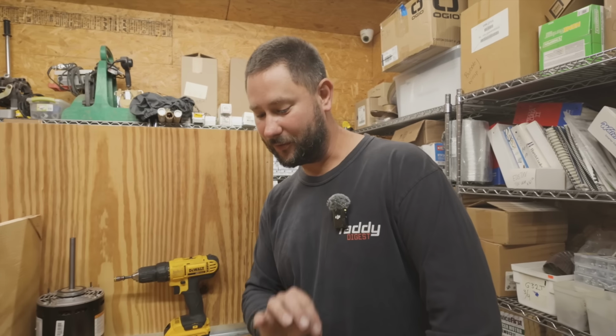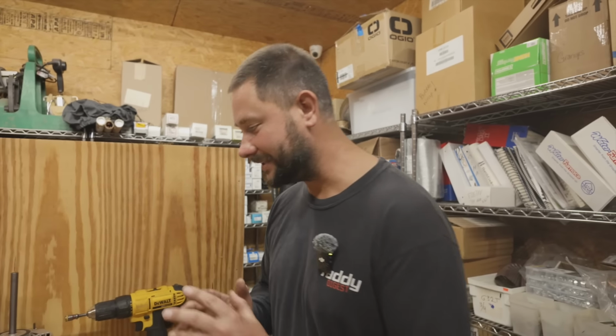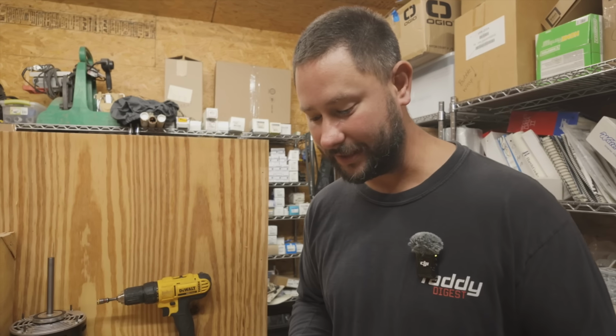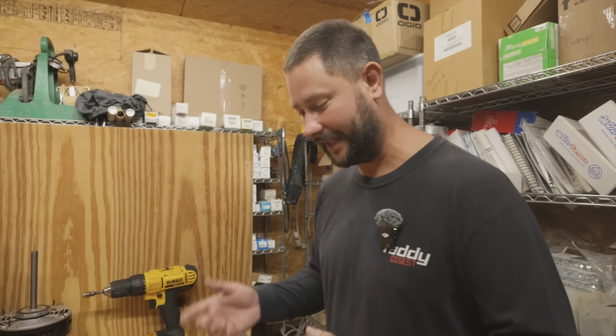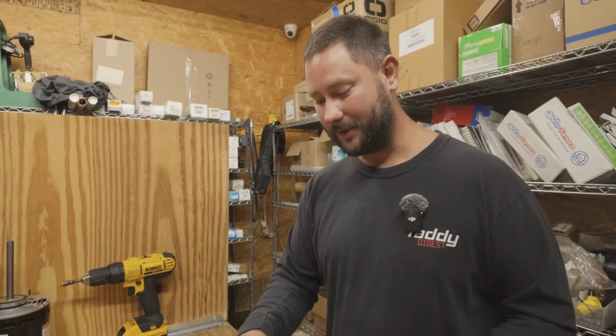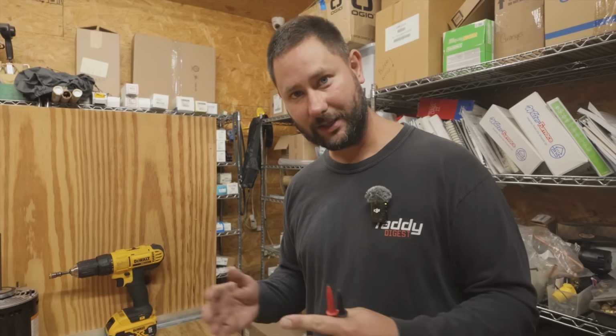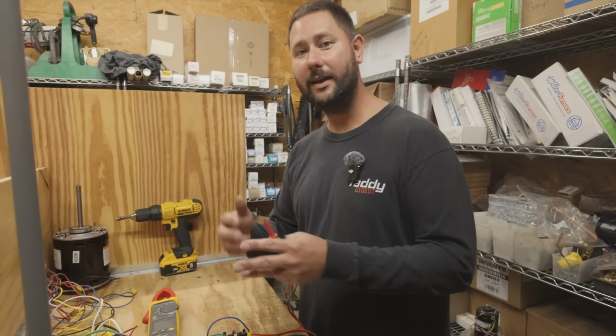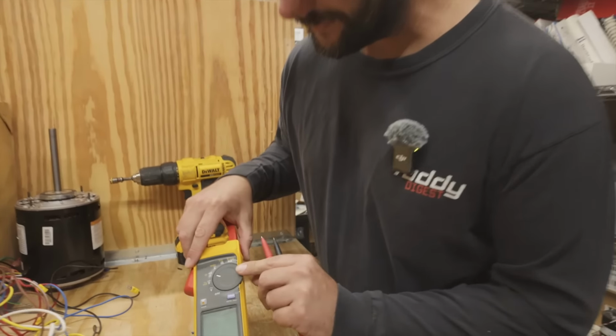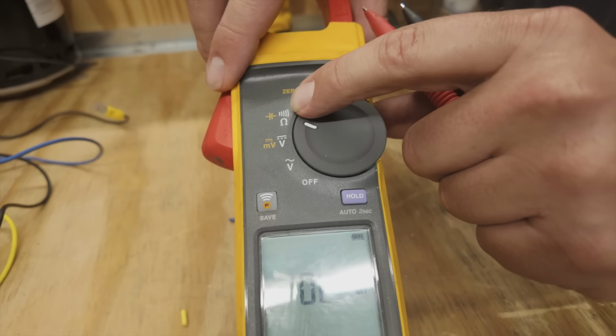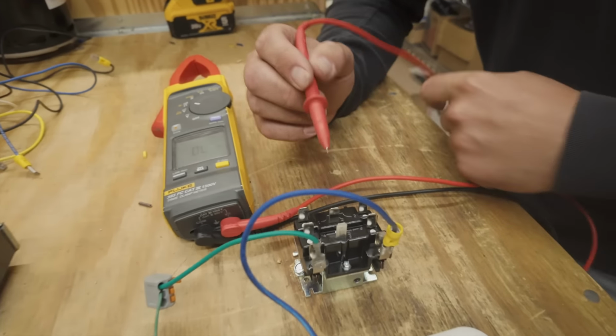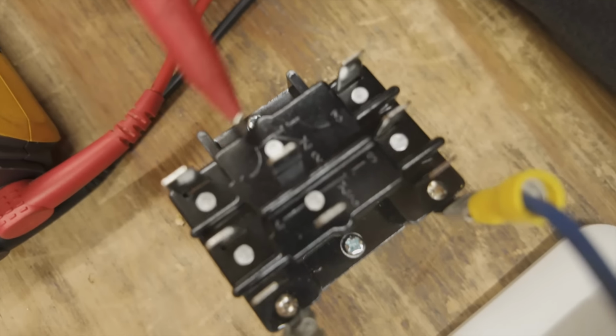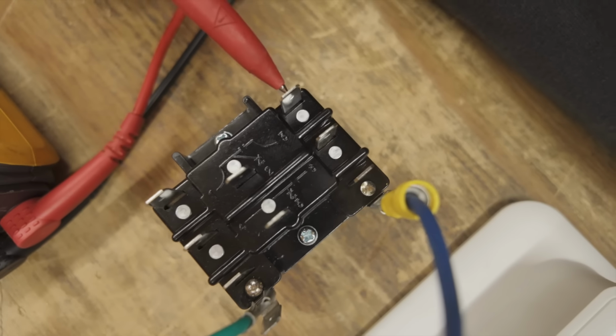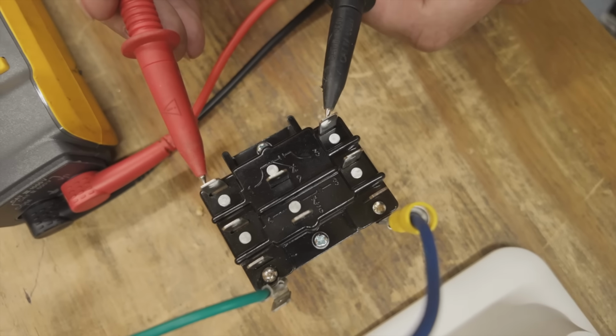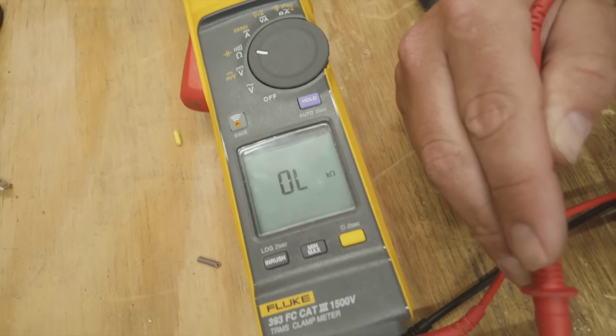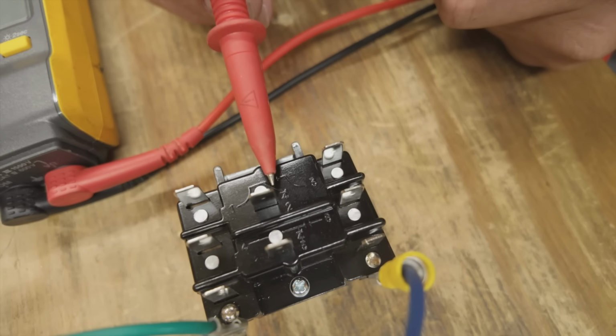Let's move forward. Now, before we hook up the fan motor and use this relay to actually send power to that fan motor with the closing of the relay, whenever it's energized, the coil receives that call, that 24 volts. I want to show you what happens to each of the contacts. We've got normally closed and normally open, before we have power and then when we have power. So take our dial and put it on the continuity symbol, looks like little waves there. And from 1 to 3, which is from this spade to this spade, it's normally open. So watch, if I put my meter between the two, it's going to read OL.